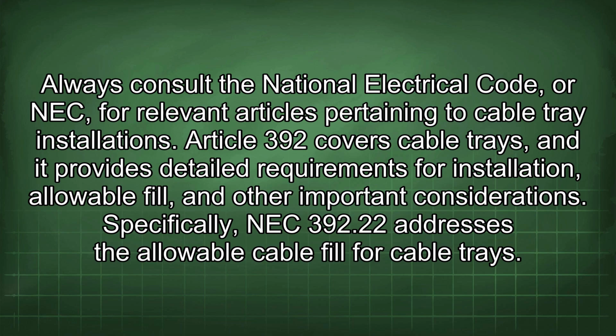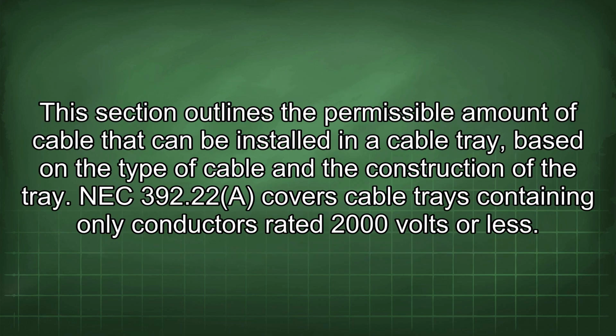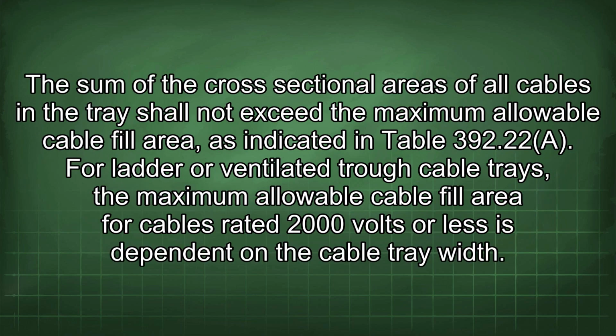Specifically, NEC 392.22 addresses the allowable cable fill for cable trays. This section outlines the permissible amount of cable that can be installed in a cable tray based on the type of cable and the construction of the tray. NEC 392.22(A) covers cable trays containing only conductors rated 2000 volts or less. The sum of the cross-sectional areas of all cables in the tray shall not exceed the maximum allowable cable fill area, as indicated in Table 392.22(A). For ladder or ventilated trough cable trays, the maximum allowable cable fill area for cables rated 2000 volts or less is dependent on the cable tray width.